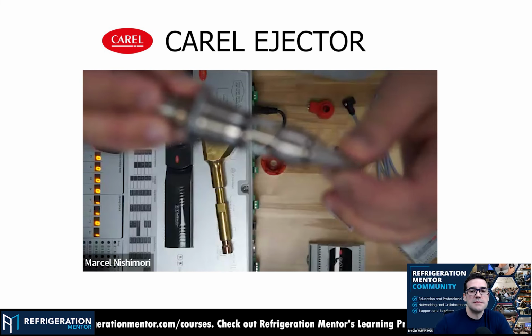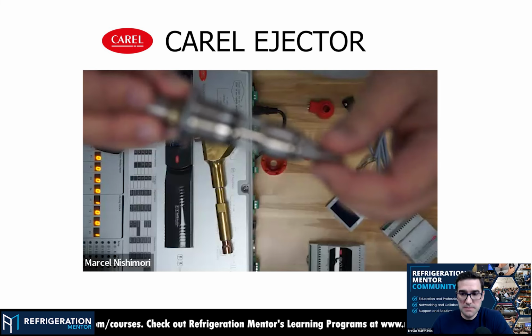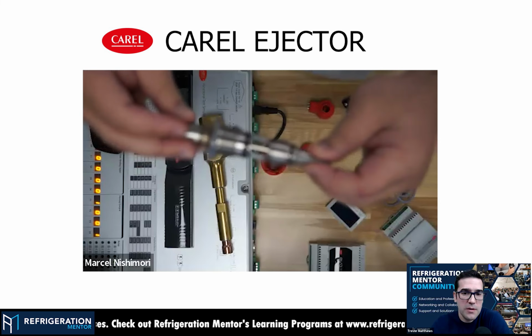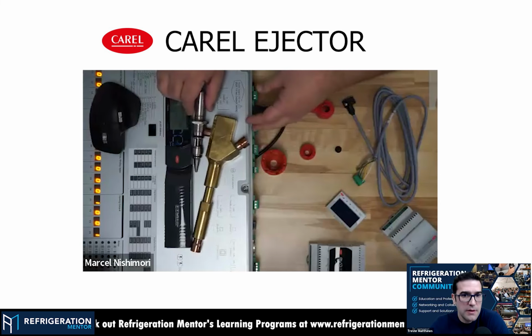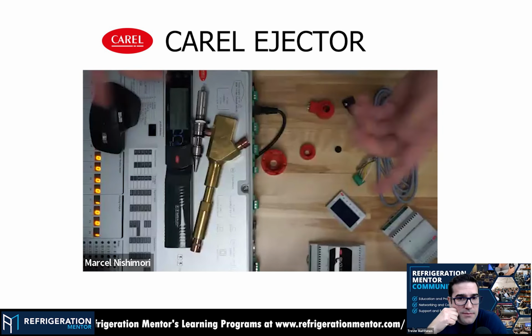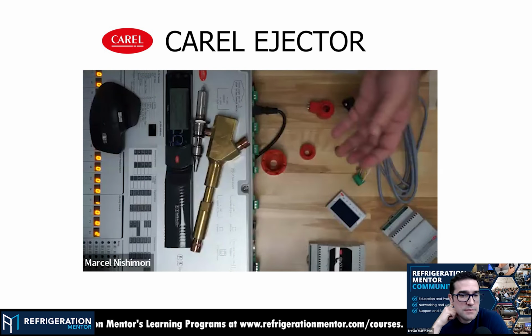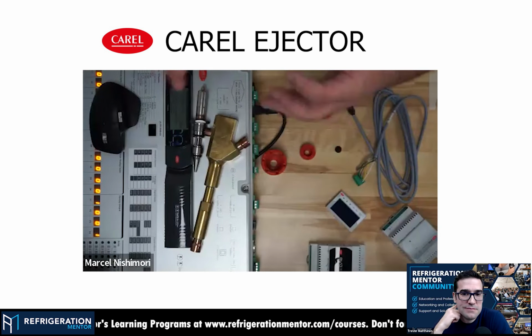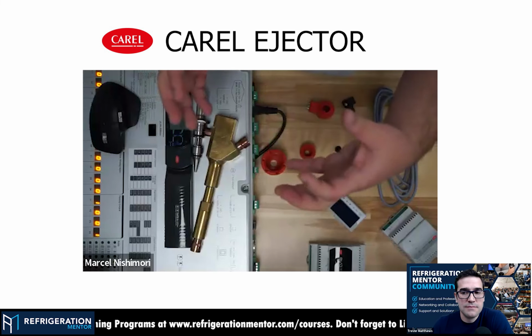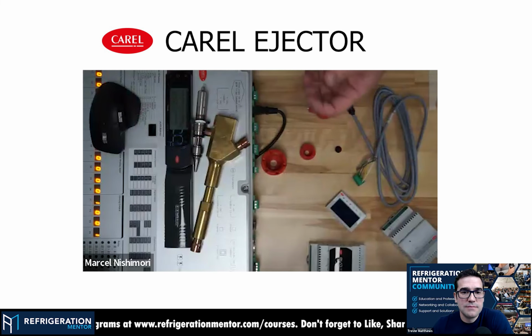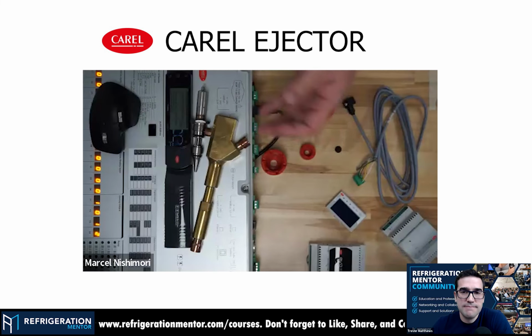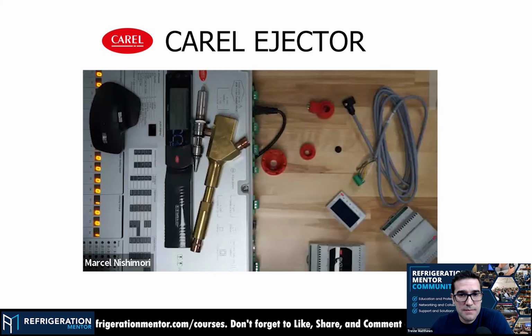Yep. So when we are designing these systems with our customers, we always recommend they have a filter prior to the ejector inlet. There is no need for a special process to run the system before activating the ejector during commissioning, but you would be recommended to have a filter before the ejector to restrict any dirtiness that could be inside the system.